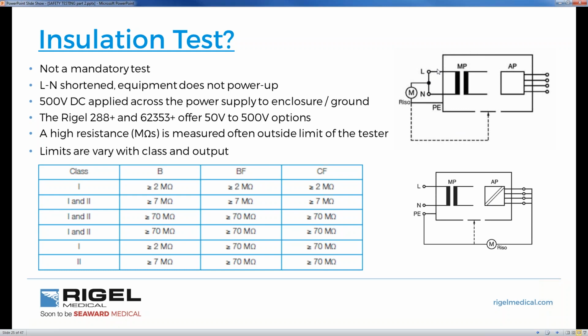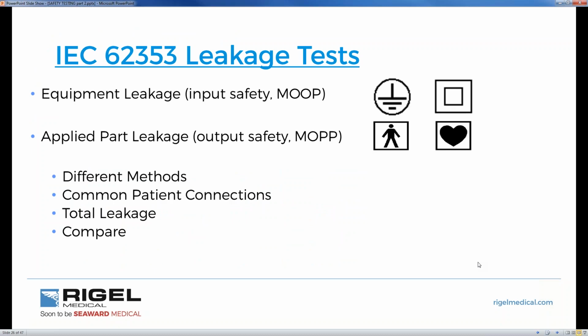So this would be a general class 1, class 2. This is our applied parts. So this would be our means of operator protection. This would be our means of patient protection, where we're putting a large voltage between our applied parts and our protective earth, and we measure what the resistance is.